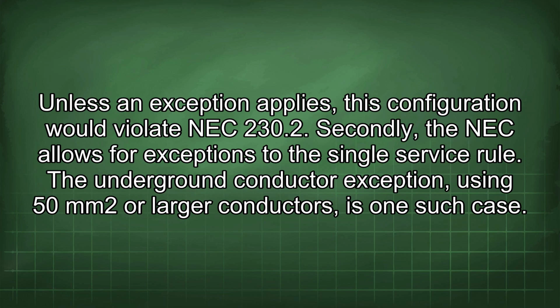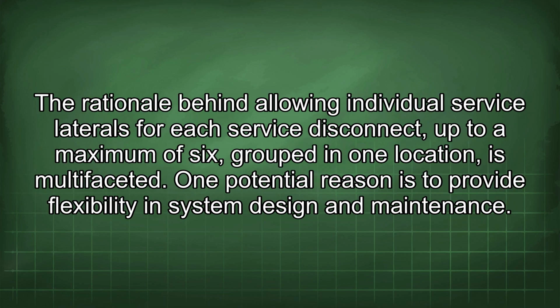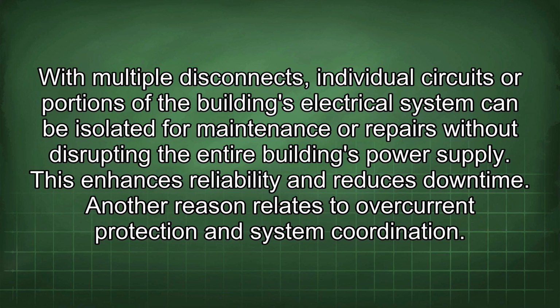Secondly, the NEC allows for exceptions to the single service rule. The underground conductor exception, using 50 mm2 or larger conductors, is one such case. The rationale behind allowing individual service laterals for each service disconnect, up to a maximum of 6, grouped in one location, is multifaceted. One potential reason is to provide flexibility in system design and maintenance. With multiple disconnects, individual circuits or portions of the building's electrical system can be isolated for maintenance or repairs without disrupting the entire building's power supply. This enhances reliability and reduces downtime.